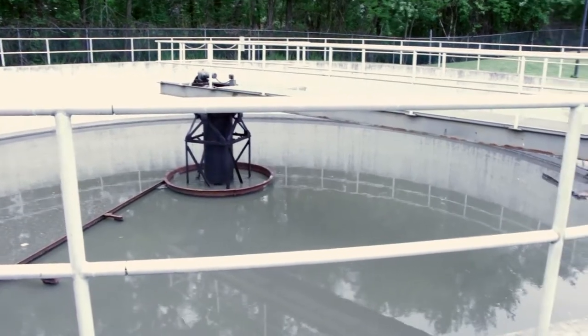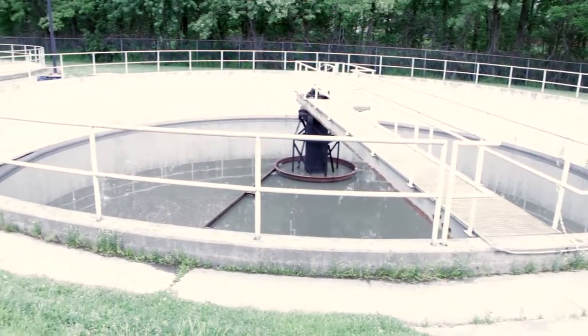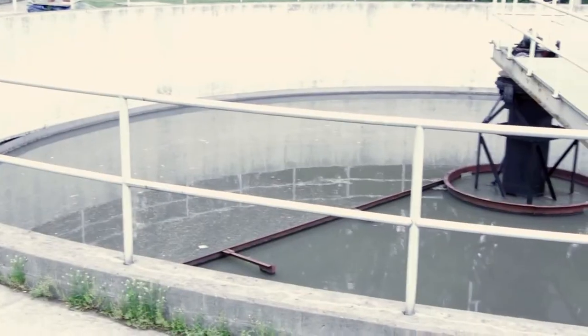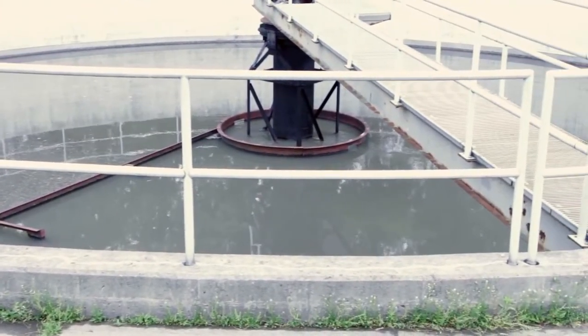Right here in the primary you get the quiescence. The floatables come to the top, they separate from the water, and the sludge sinks to the bottom. There's a skimmer arm that collects the scum as it comes out, and it goes over to this hopper right over here. We have to pump that at least once or twice a week. Once we get a good load of scum, we process it through a concentrator and it goes to a landfill for disposal.